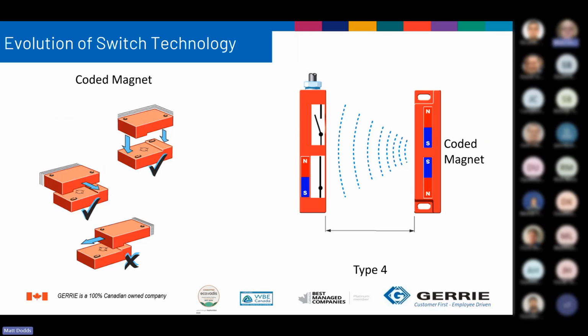Type 4 technology, these are non-contact and fall into three categories: magnetic, RFID, and optical. All require coding of some degree. Magnetic coding uses a series of magnets in the actuator, and when aligned with the sensor, they change state. Direction of travel is important because there are two contacts in there. So as the actuator moves, it could actually transition the set of contacts a couple of times, which would result in an error of the controller.